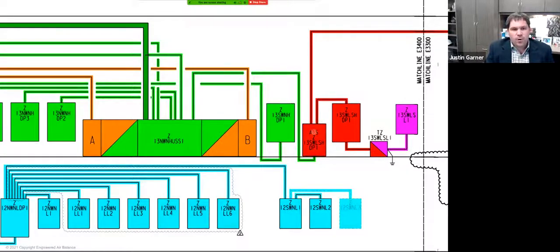The way that these ATSs work is they're going to monitor their primary source, which in this case happened to be the utility source. If they see that source fail, is not present anymore, then this ATS is going to send a signal down to the paralleling gear that controls the generators, or maybe directly to the generator itself, and it's going to tell that generator to start and that it needs power. And then as soon as that generator starts and it's up to speed and generating power at the right voltage and frequency, then this ATS will automatically transfer to this alternate source and thus provide power to this distribution panel and anything downstream.